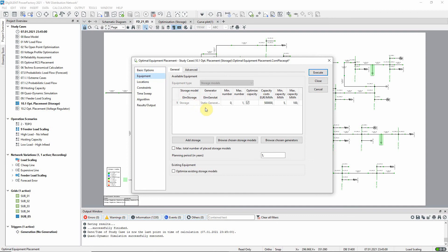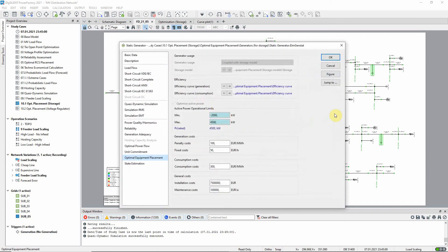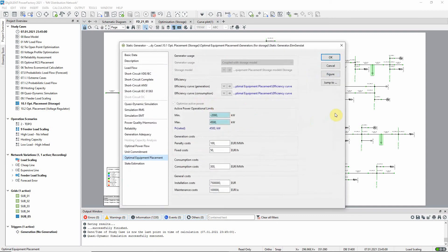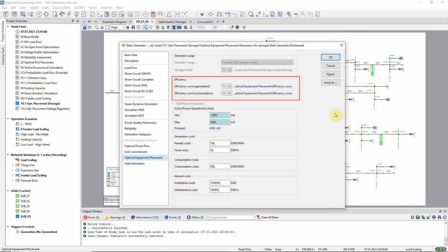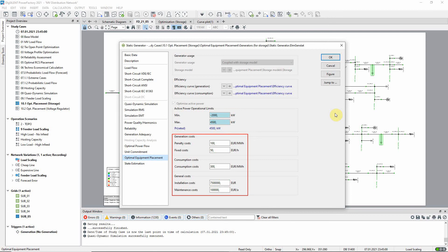On the equipment page the equipment to be added can be configured in the static generator. On the optimal equipment placement page we can see that efficiency curves have been selected and the active power limits for charging and discharging the storage device have been specified. The installation and operating cost data are also entered here.